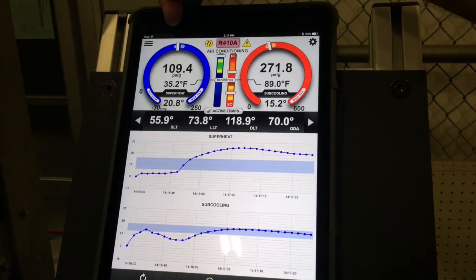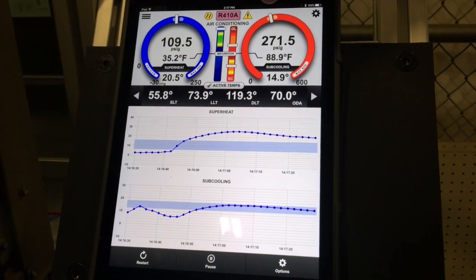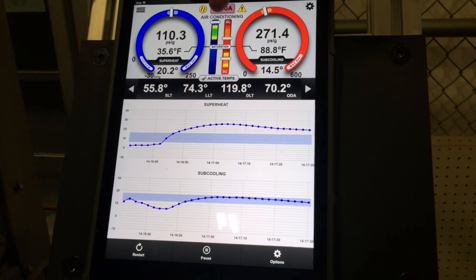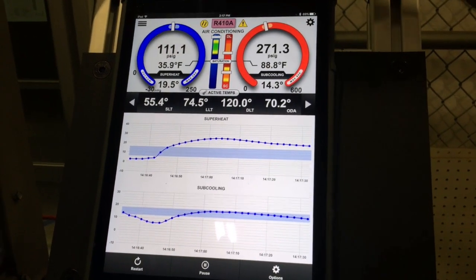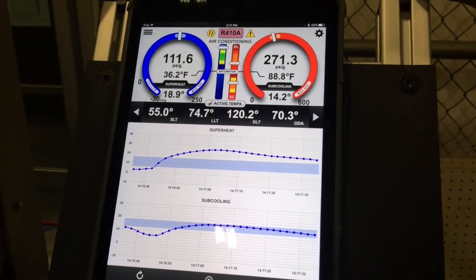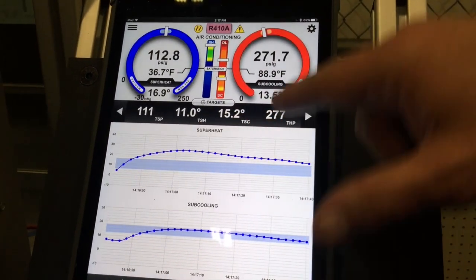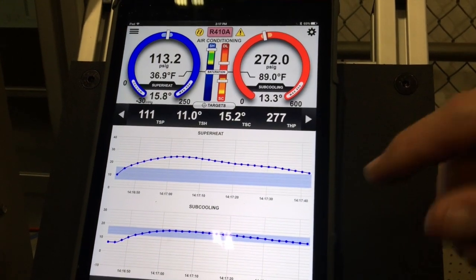You can see very quickly that the pressure is coming to line very fast. Our superheat's not quite down yet where it should be. We're at 20 degrees of superheat. Our target's somewhere around 10 to 12. I can take a look here real quick. Our target is 11 degrees of superheat, 15 degrees of subcooling. So we'll let that thing stabilize.